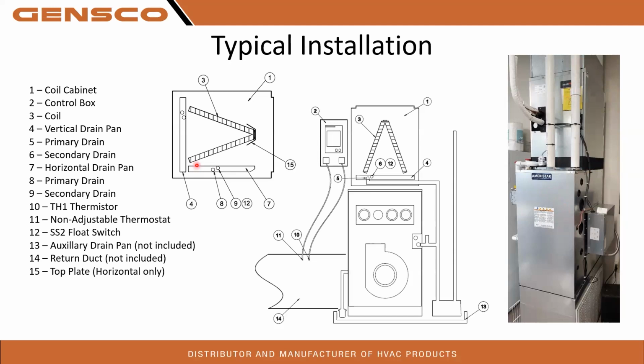A couple things to notice on here: on a horizontal application, you have a drain pan and a top plate on this thing. In a vertical application, those are gone. If you're going to use a vertical, horizontal up or vertical up or vertical down, you'll need to make sure to remove those. Horizontal left or horizontal right, you will have those in there. These things come pre-shipped from the factory in the horizontal right position. So if you need to change that to the horizontal left, you'll take the drain pan out along with the brackets and move it to the other side. We have some slides coming up that'll show that a little bit better.